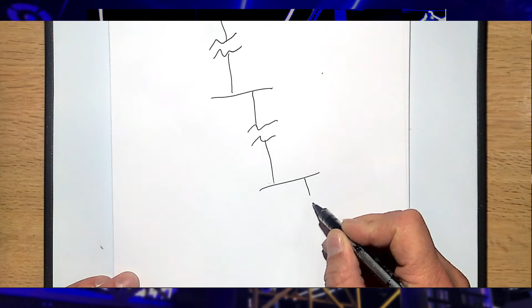This capacitor will resonate with this series combination of inductance. This capacitor will resonate with this transformer. If I make them into harmonic filters, I want to put that filter at the lowest level that I can, close to the load, because I want to absorb that current before it goes up through the transformer. When I say absorb, it goes out on phase A, goes through this, and goes back on B and C. So the harmonic current just gets exchanged in this loop. If I don't have a filter here, the harmonic current flows up, maybe even all the way back to the source, and flows back down through the system.